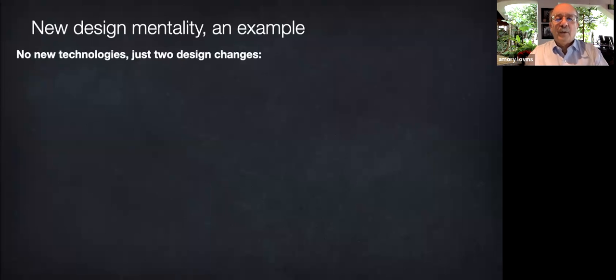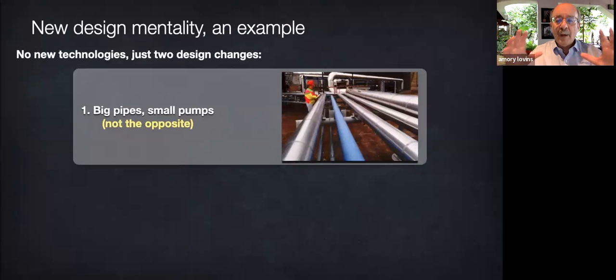How do we do this magic? We make two changes in the design process, the design mentality. First, we specify big pipes and small pumps, not small pipes and big pumps. Friction in a pipe falls as nearly the fifth power of its diameter. So how fat should the pipe be to optimize the friction? The textbooks say to make the pipe just as fat as will repay its extra cost over the years from the saved pumping energy. Sounds plausible, but it's wrong because it leaves out the capital cost of the pumping equipment.